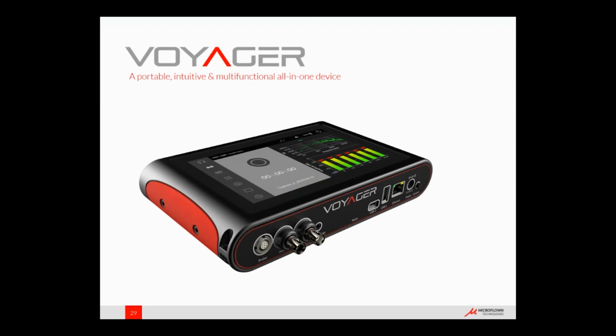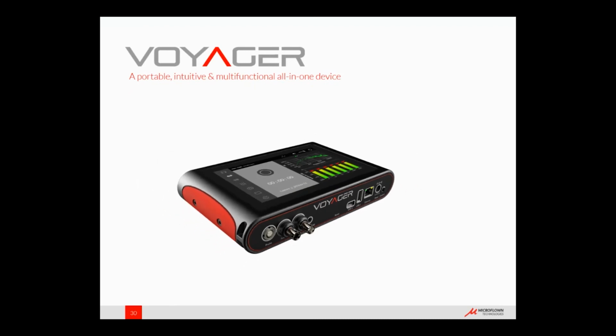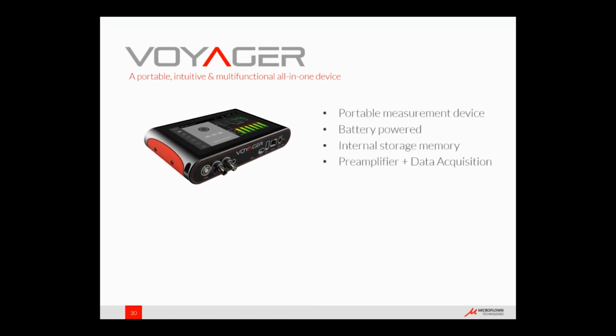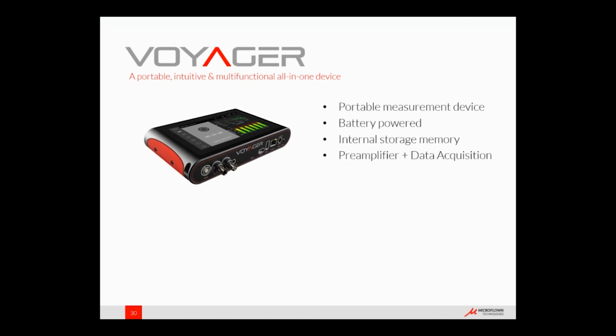It merges the things that we mentioned before into just one single device. It's a portable measurement device with a built-in battery, so it can be used completely battery operated. It has internal storage memory to store the data. It has the preamplifier plus data acquisition built in.